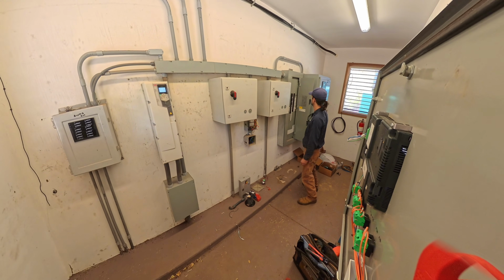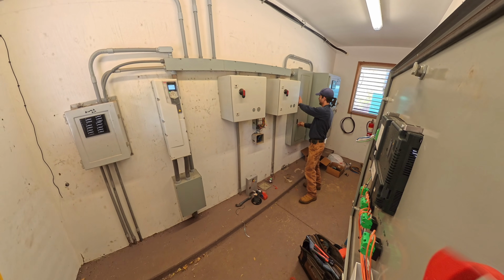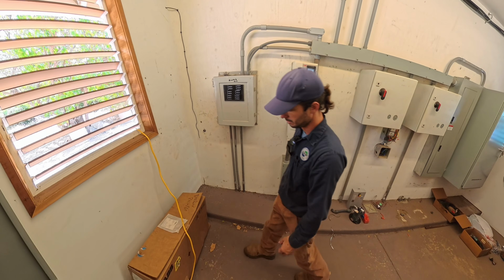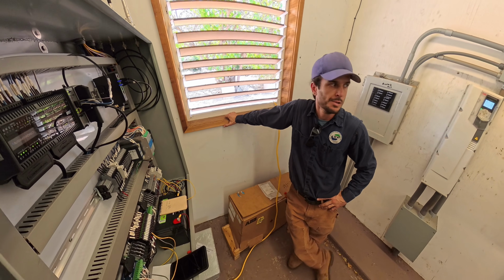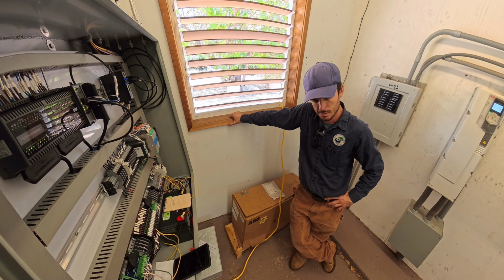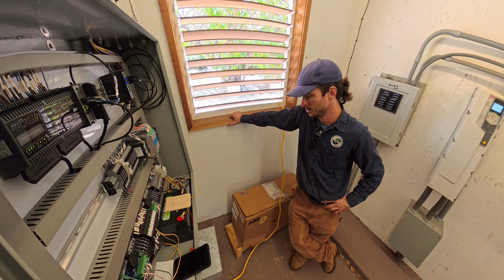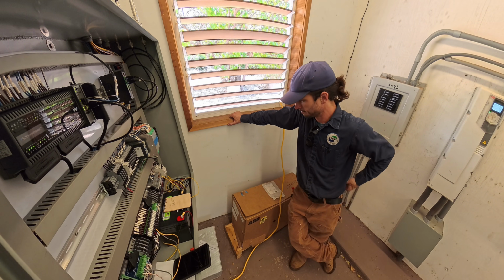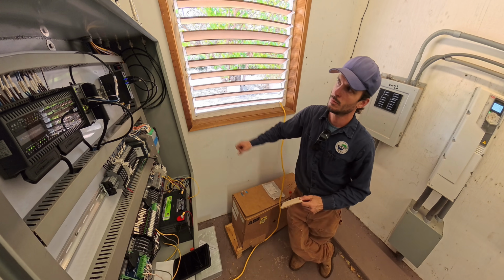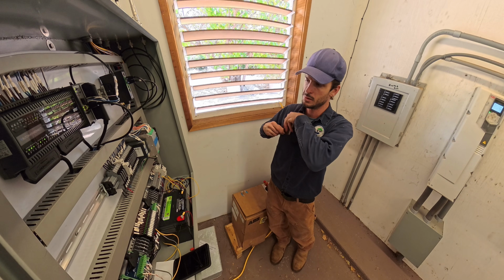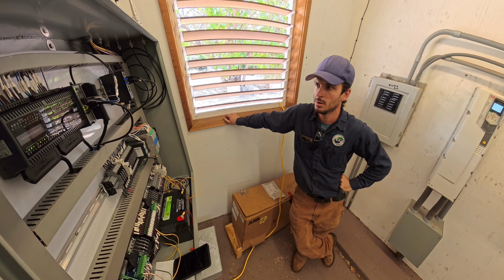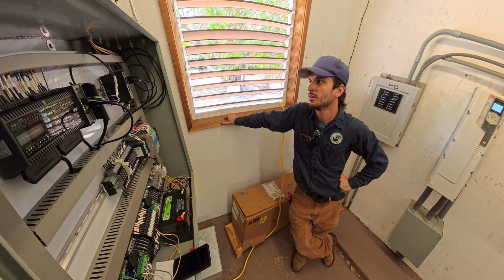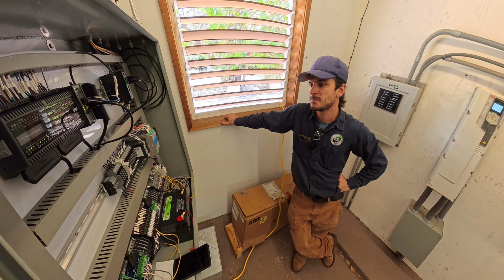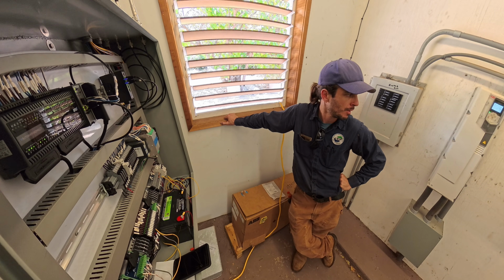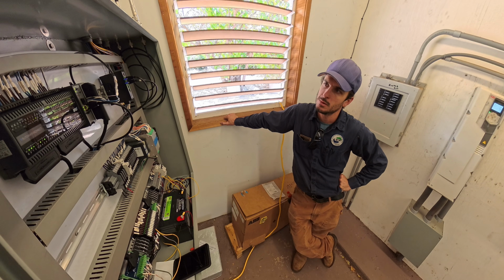Okay, and it opens on fault, you said? Yeah, opens on fault. Load, high. Okay, there we go, so right now I'm seeing it as energized, which means that the float is not active, aka run the pump, right? Yeah, the float is up, so we're good, pump can run. Yeah, run pump. So energize when we want to run the pump. Yeah, okay, zero stop pump. Okay, let me.